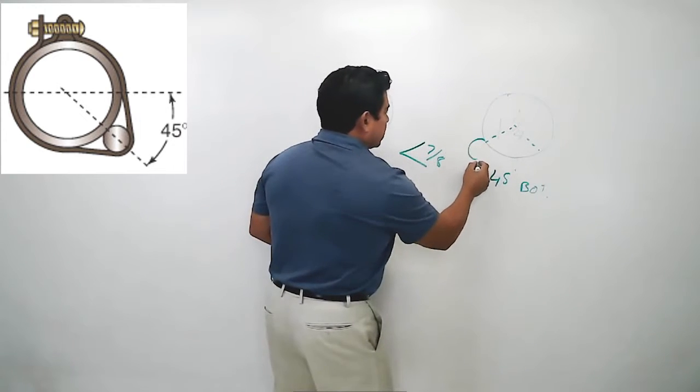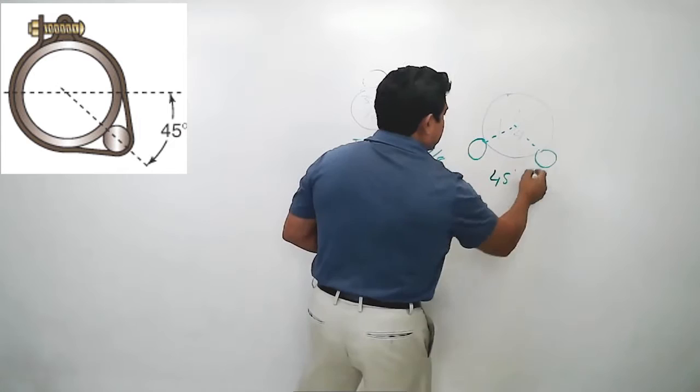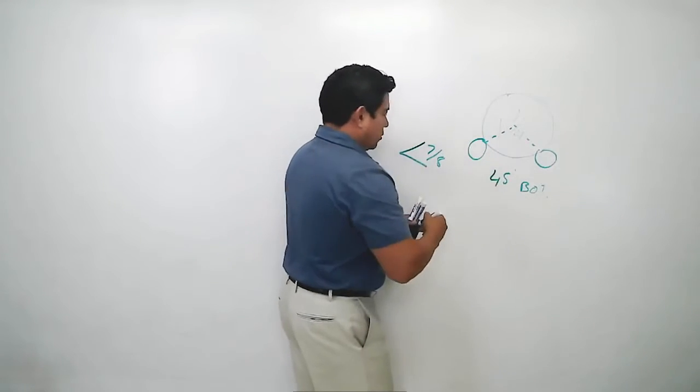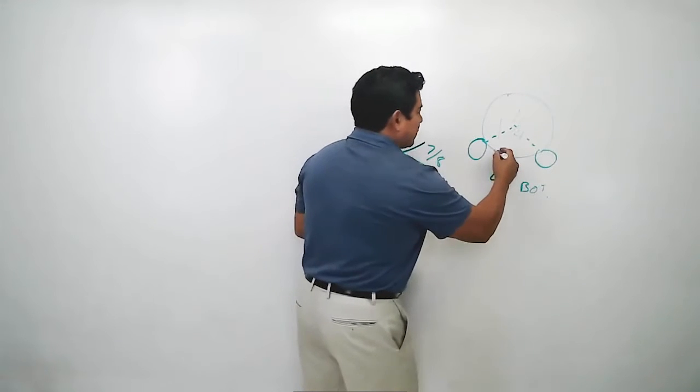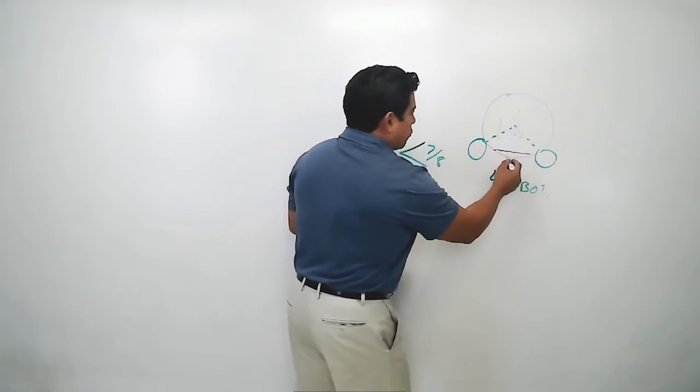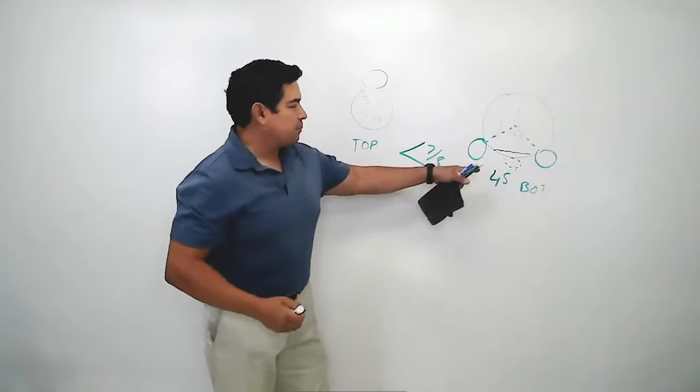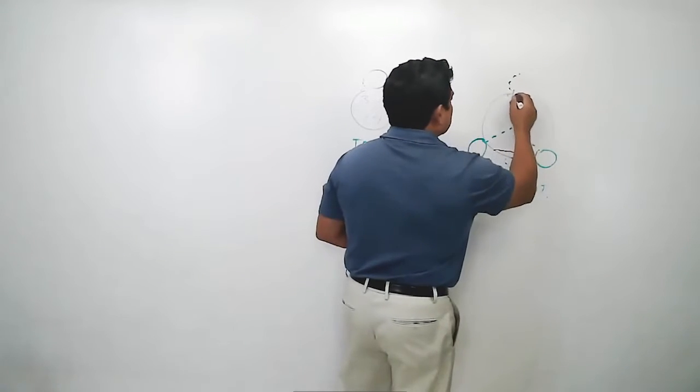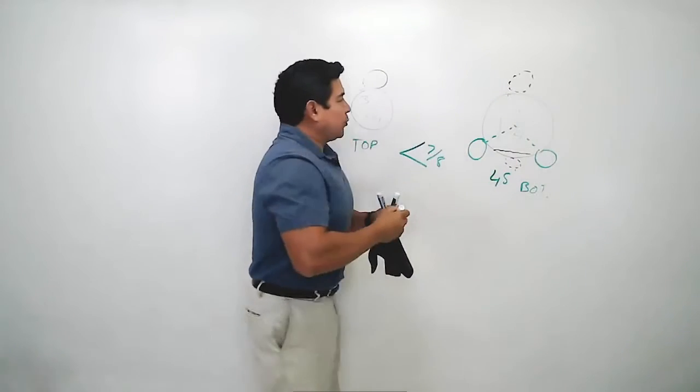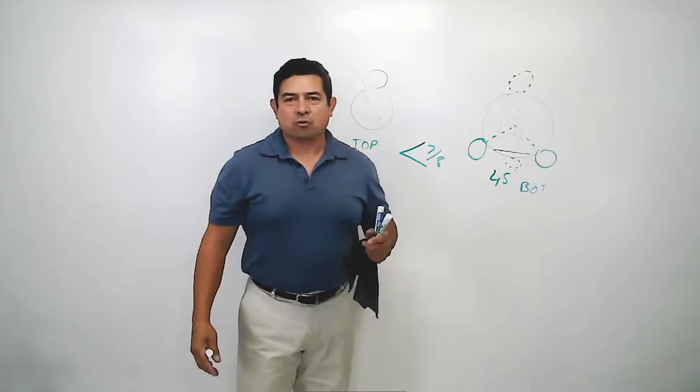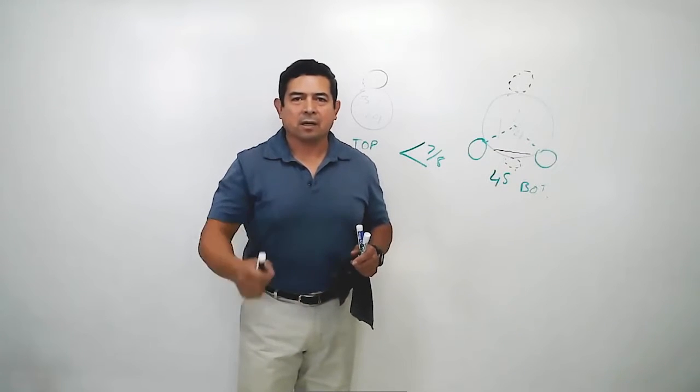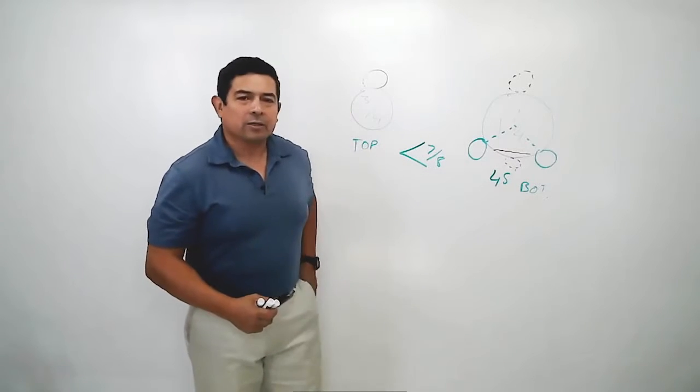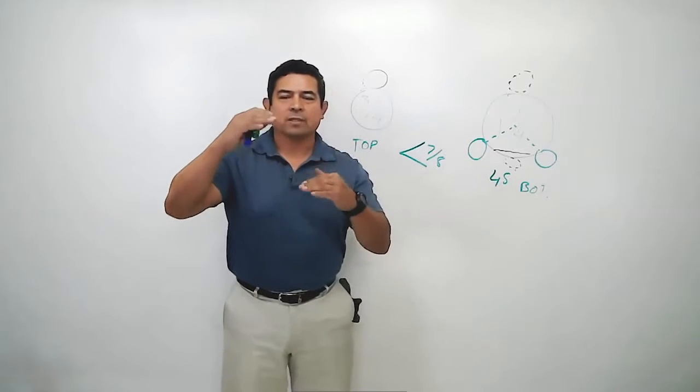The reason we do that is because traveling with the refrigerant, we might have some oil. So we don't want it down here because then it's going to be sensing the temperature of the oil. Also, we don't want it up on top either. The reason for that is because of stratification. Stratification is when you have layers of gases or layers of liquids, layers of fluids.